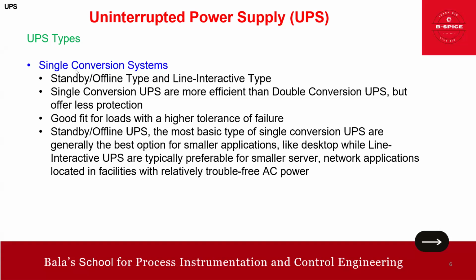So single power, single conversion, we have standby offline and line interactive. The standby offline UPS, the most basic type of single conversion, is generally a good fit for desktops. Another one is line interactive, typically preferable for a smaller server or network application. Got it, friends? Good.